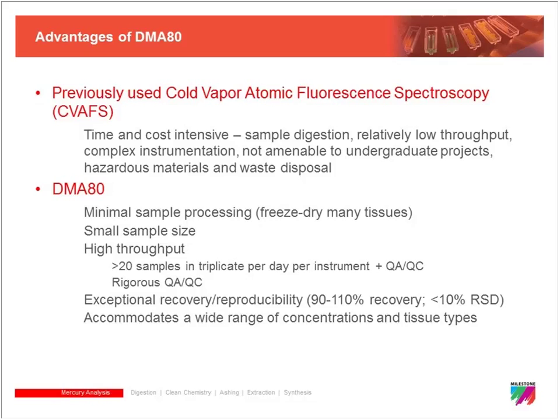If you have samples with a high concentration, you can decrease the actual sample that you run and keep it within the calibration range of the machine as well. So, for instance, with hair, we have sometimes run samples as low as 6 milligrams at a time, and it really depends on how good your scale is. Most of our other tissues, we typically run at about 30 milligrams of dry tissue, since we're mostly doing dry samples.